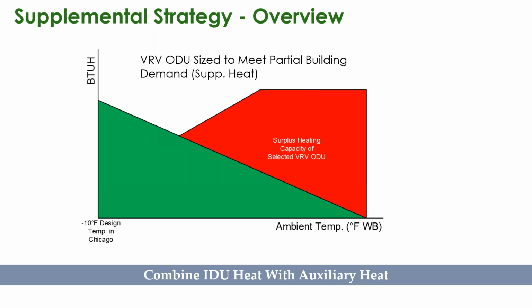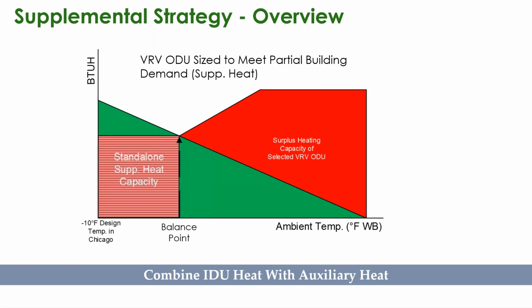So on your typical curve, when you're plotting this, again, your load profile is the thing that is going to dictate where you're going to size your outdoor unit to determine your balance point. Your supplemental heat is going to be sized to meet the capacity up to that balance point. So that way, if there is a failure, you're not covering the entire load requirement, but you're covering enough of it. And that is why I say it's more mild cold climates that this is a common practice in. That reduces the upfront costs while still allowing some heat to be delivered in the event of a total failure. We're expecting that the variable refrigerant system will be running and it will be able to pick up the rest of the demand to finish out your load requirements.